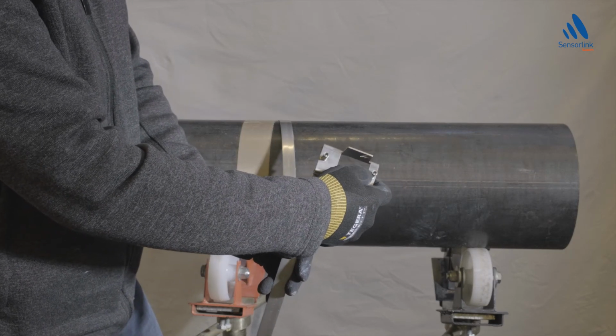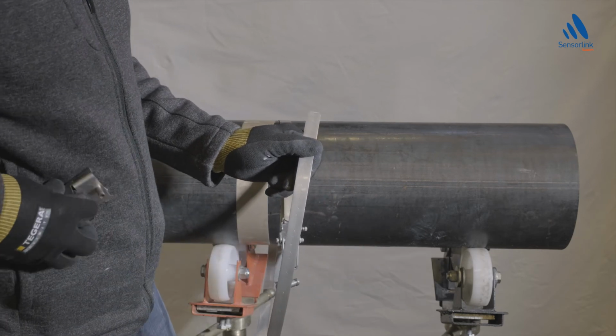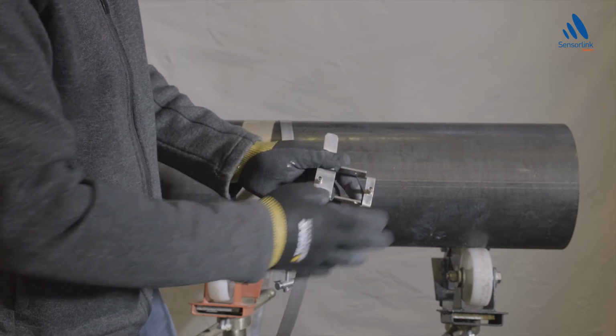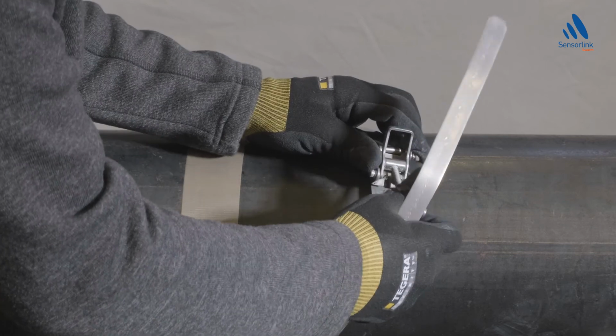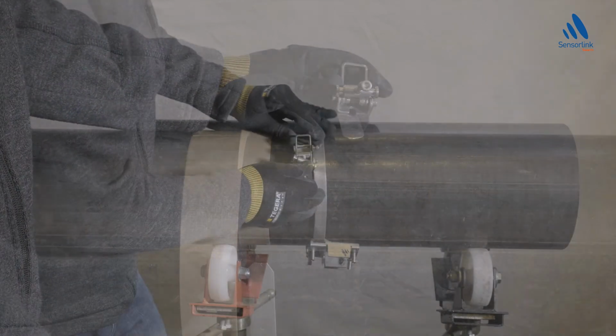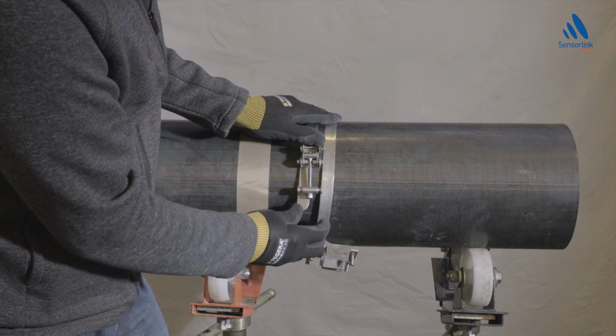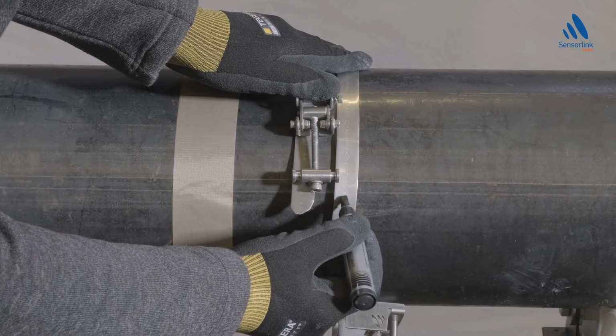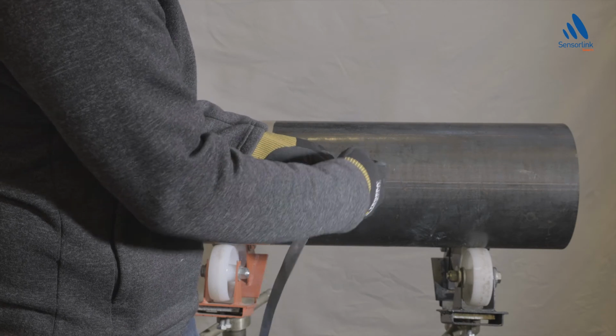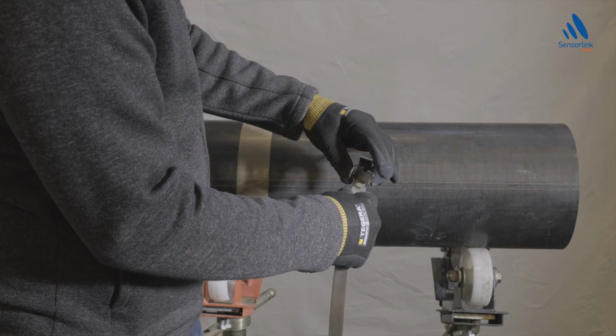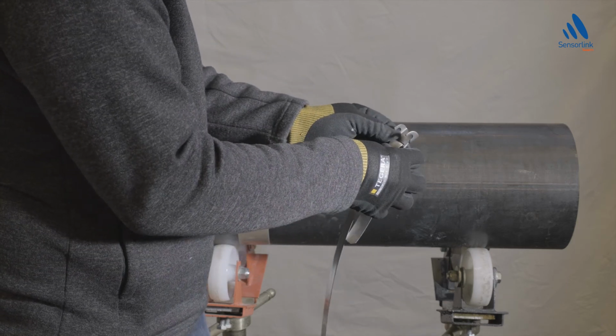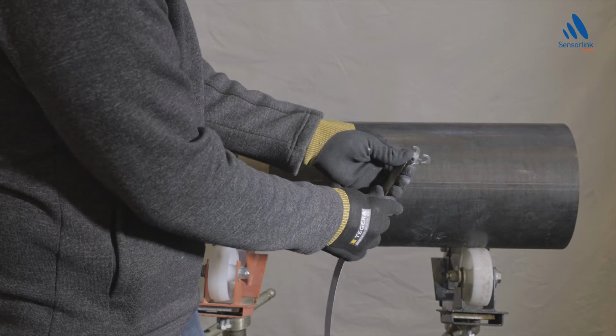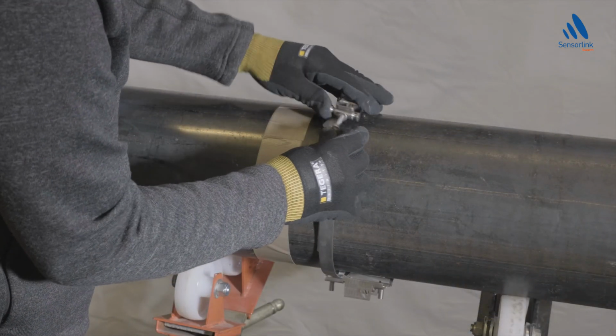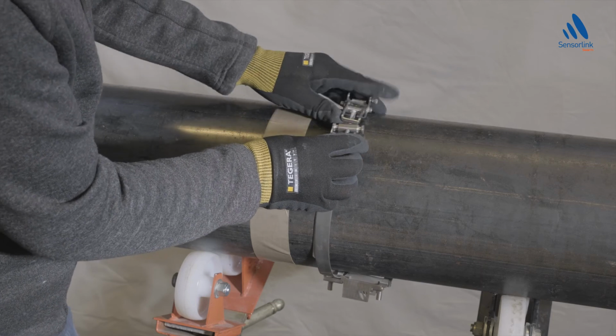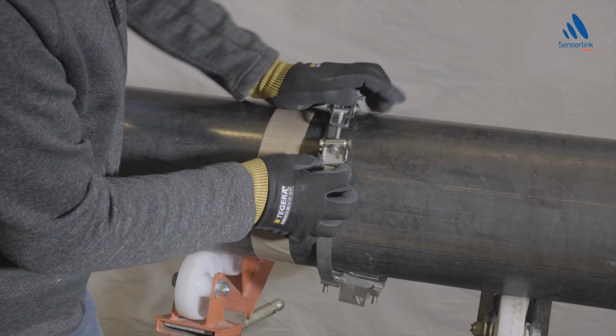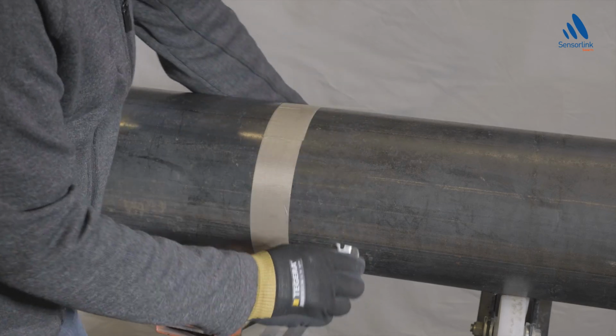Insert the free end of the band into the brackets to be installed. Wrap the band including brackets around the pipe. Make sure that the tightening bolt is loosened to maximum length and the buckle arm is in closed position when doing this step. Make a mark on the band aligned with the bolt head. Attach the buckle hook and make a soft bend at the marked length. Wrap the band around the pipe. Adjustment of the band length may be necessary if you are unable to hook on the bolt pin. Open the band, take off the buckle hook and adjust the length.